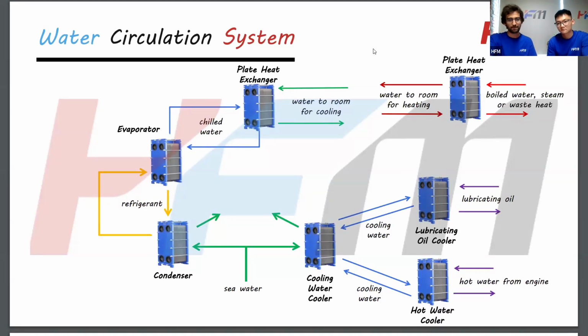So here we go. The material for the cooling water cooler is generally going to be titanium for the plate and NBR for the gaskets. For the hot water cooler and the lubricating oil, it's going to be stainless steel, either 304 or 316, and the gaskets in NBR.